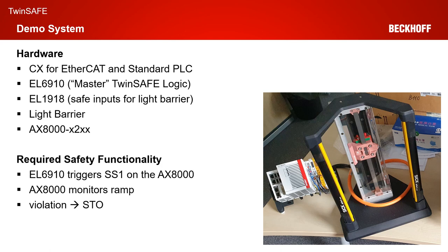The required safety functionality for today is to trigger SS1 via the EL6910 on the AX8000. Then the AX8000 monitors the ramp and a violation of the ramp results in STO.